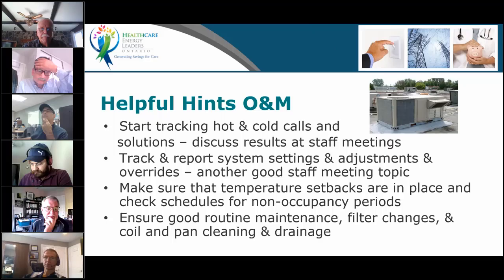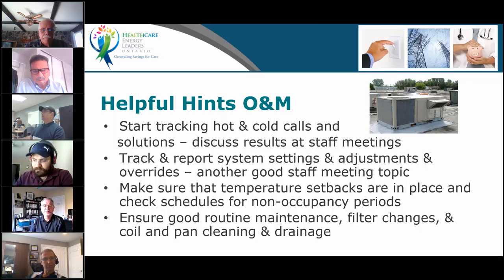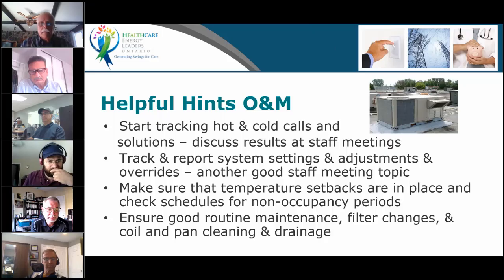Be very wary of those standardized measures where somebody comes and says, hey, we're doing that everywhere. That doesn't mean it should be there. A heat recovery wheel that is not recovering, unless you have a bypass, will cost you money. It will have a 1-inch delta P, a 1-inch pressure drop, which you will pay at all times when the fan is operating. So always look at the entire picture.